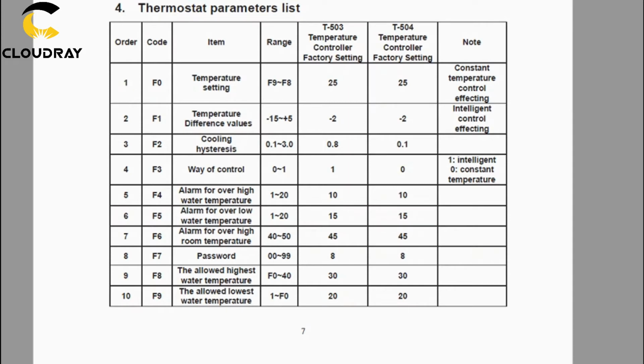So what I'll need to do first is change the setting for F9 to be a bit lower than 20. For example, if I want to set this at 18 degrees on F0, it won't allow me to. So we need to change F9 first, bring it at least down to 18 degrees, then go back and change F0 to be constant at 18 degrees. So we'll have a quick look at this again.